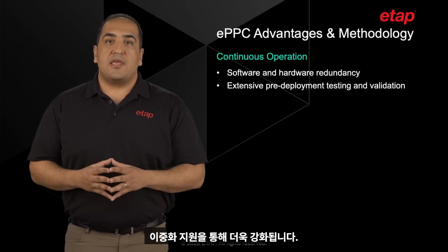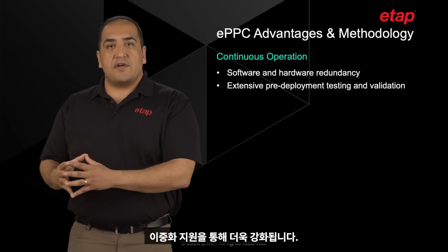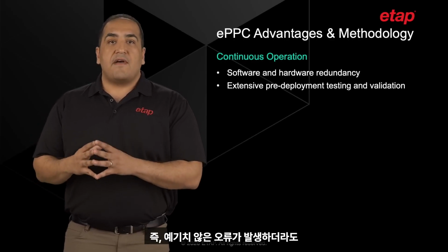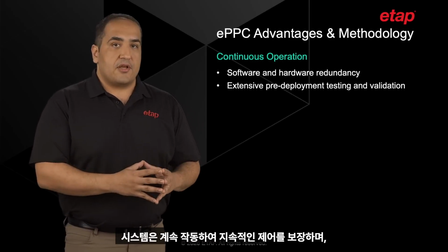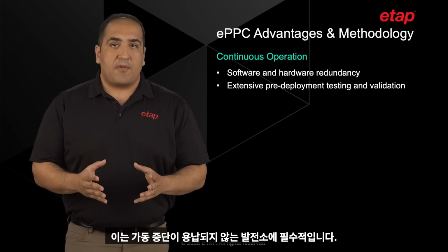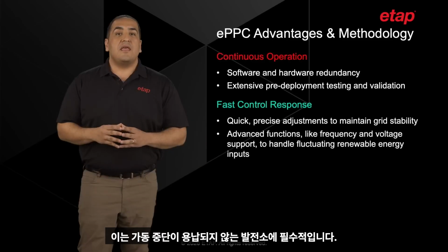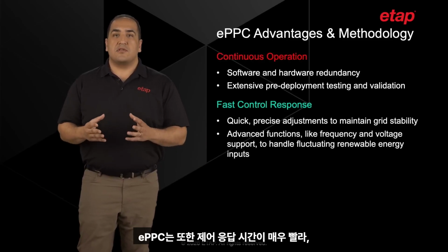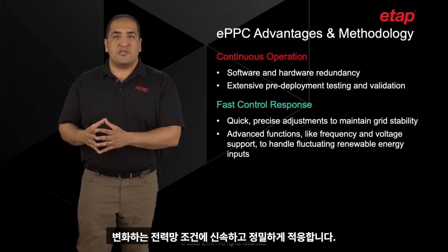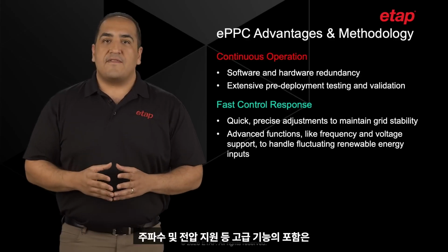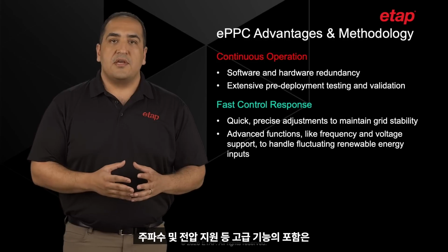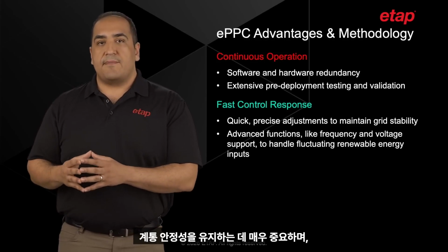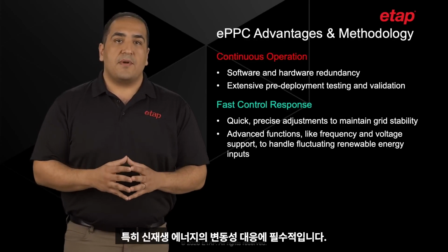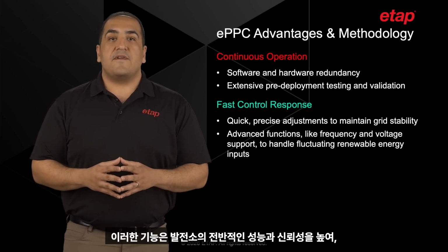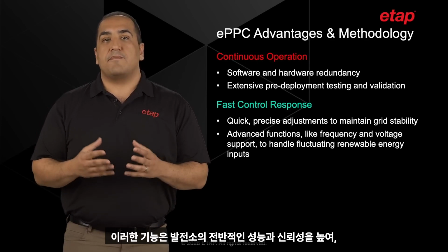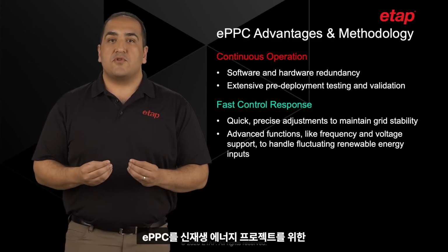Reliability is further reinforced by ePPC's support for both software and hardware redundancy. This means that in the event of an unexpected failure, the system remains operational, ensuring continuous control, which is vital for power plants where downtime is not an option. ePPC also excels in providing fast control response times, enabling quick and precise adjustment to shifting grid conditions. The inclusion of advanced functions such as frequency and voltage support is particularly important for maintaining grid stability, especially in the face of fluctuating renewable energy inputs. These capabilities further enhance the overall performance and reliability of the power plant, making ePPC a future-proof solution for renewable energy projects.